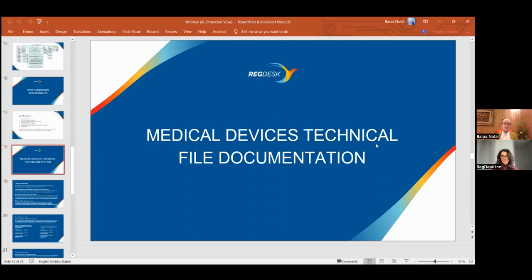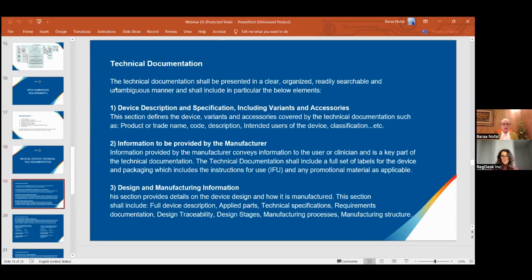So you need to keep in mind all the documents I will show you, that you need to prepare in order to not lose your file or receive any rejection. So the technical file will include, and I will set out only the highlights of the requirements. The first one is you need to provide the device description and specification, including variants and accessories. And the second one is information to be provided by the manufacturer.